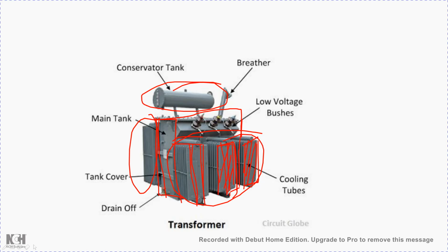Now the cooled oil will flow back inside through this pipe from the lower side. So hot oil comes to the upper side, and when it passes through these tubes inside these covers, it radiates the heat and gets cooled to a lower temperature, and it flows back inside. This process takes place continuously, and here is a breather. For the circulation of the oil we also require air circulation, so for that there is a breather. And here bushings are given.